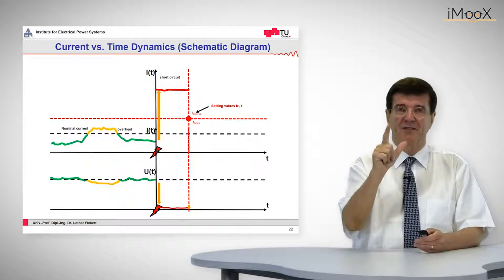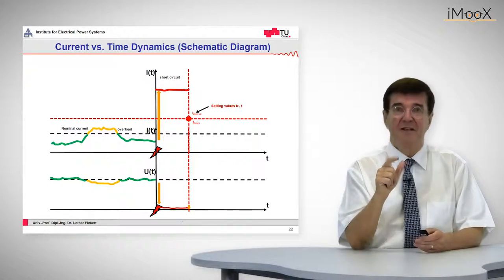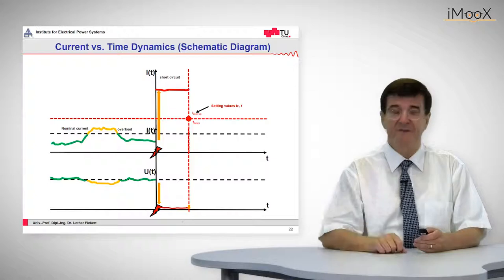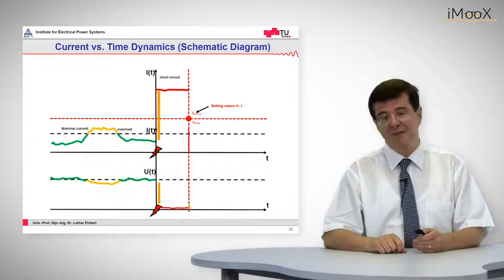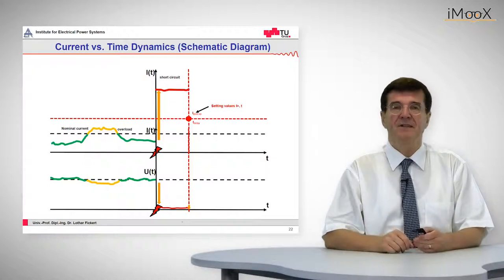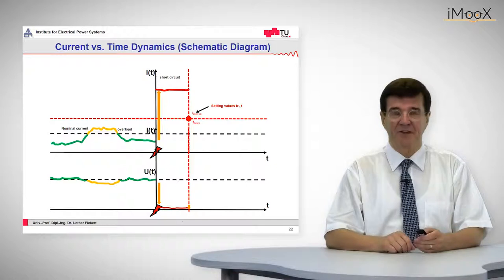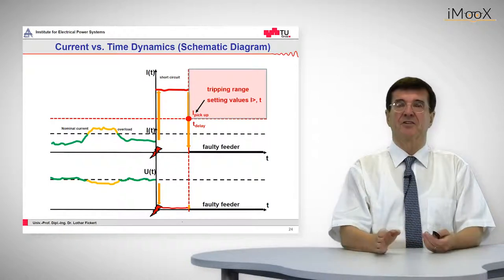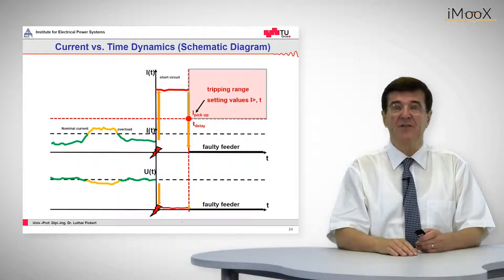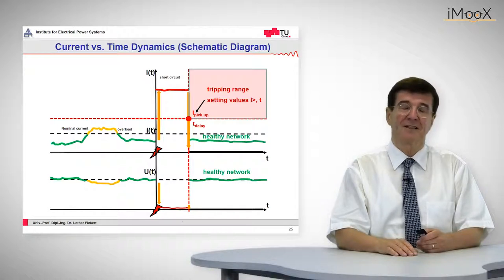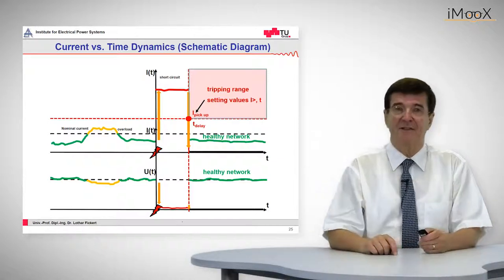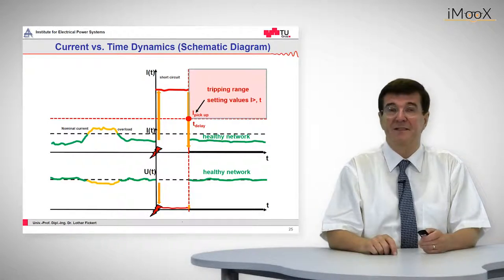The current goes on until the protection comes in. The protection has two setting values relevant at this point. The first is the pickup value, which is of course below the 5 kilo-amps so that the protection sees there is a short circuit. The second one is a time delay — for example 0.4 seconds. When this time has elapsed, the protection device will trip the circuit breaker. The current will go down to zero since the circuit breaker has opened the faulty feeder, and the voltage on the faulty line goes down to zero. The voltage in the healthy network has recovered since there is no fault anymore in the grid.